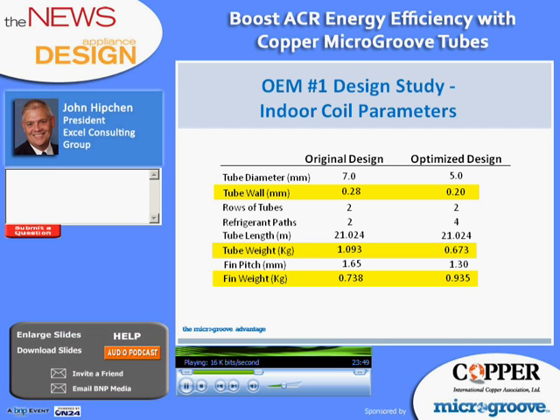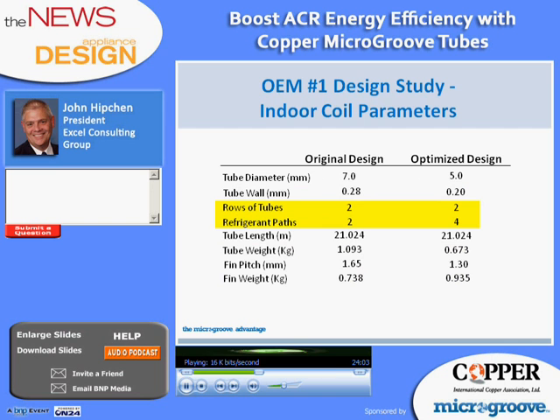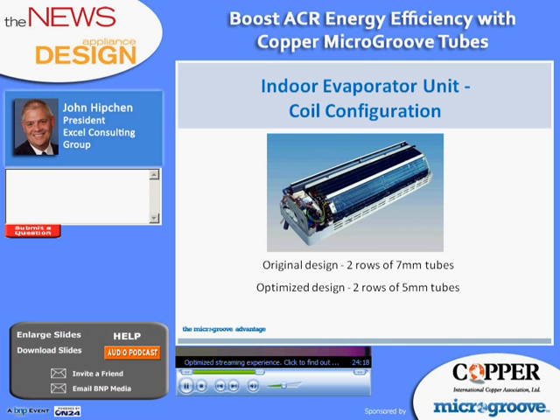Because the tube diameter was reduced in the optimized design, but not the total tube length, one might expect the pressure drop in the optimized coil to be higher. But note the number of rows and refrigerant paths. We see that the optimized coil has 4 refrigerant paths versus only 2 for the original design. A quick look at the indoor unit tells us that this coil is long and somewhat narrow.